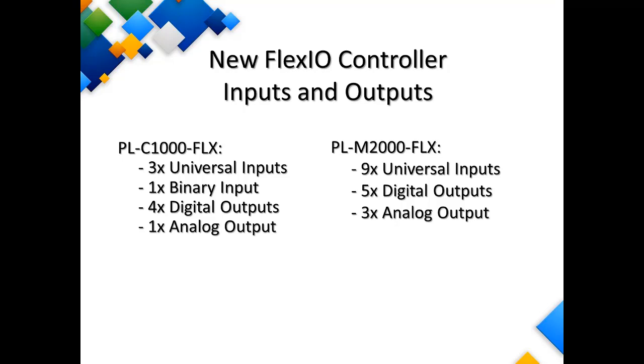It can accept a 0 to 5 volt DC signal. It can accept a 1 to 5 volts. It can also accept a 0.5 to 4.5 volts DC, because we know that there are a lot of pressure transducers out there in our industry which have this specific range. So we wanted to make sure to include that. The input can also accept a 4 to 20 milliamp signal. And well, obviously for the contact, the input would simply be a dry contact.